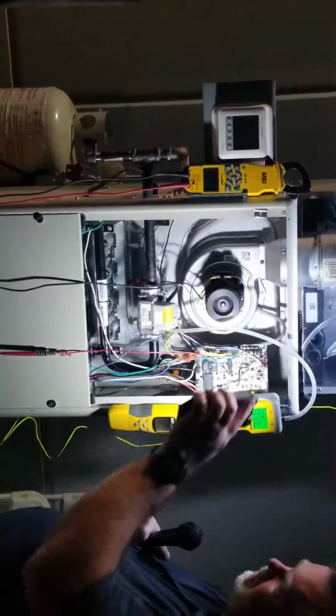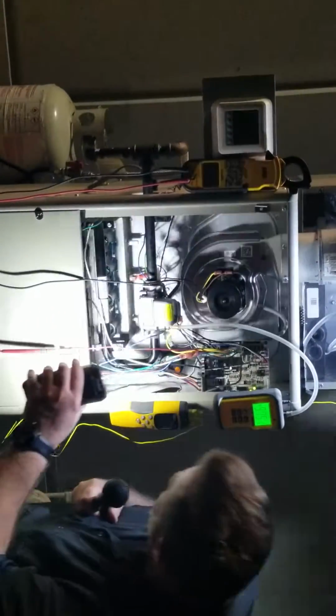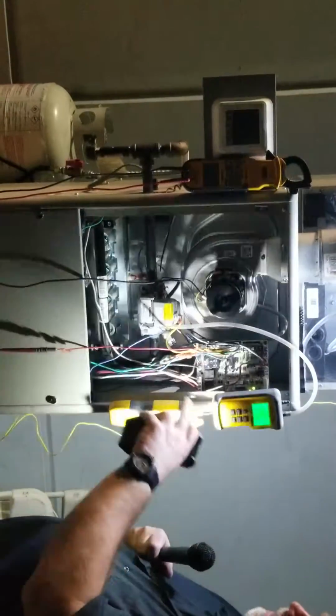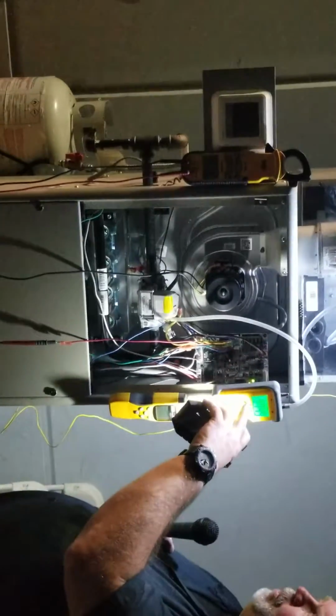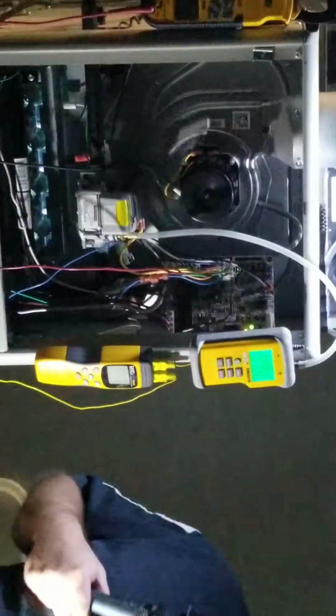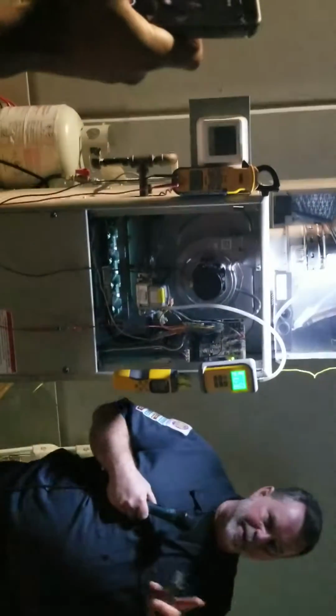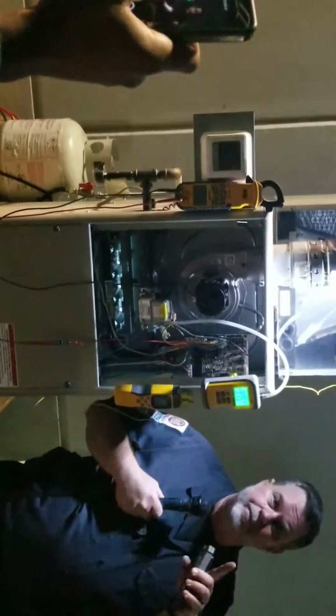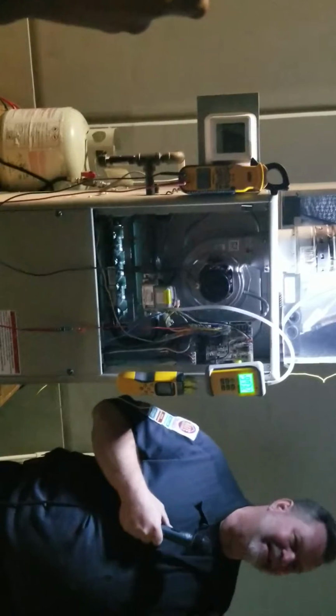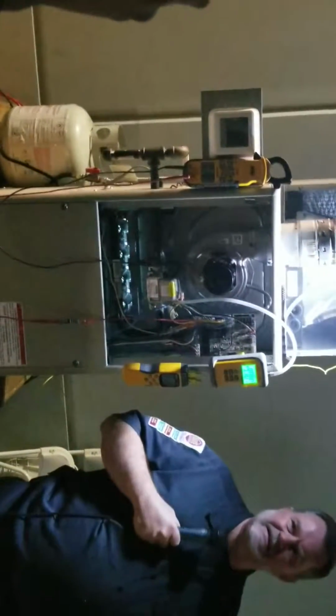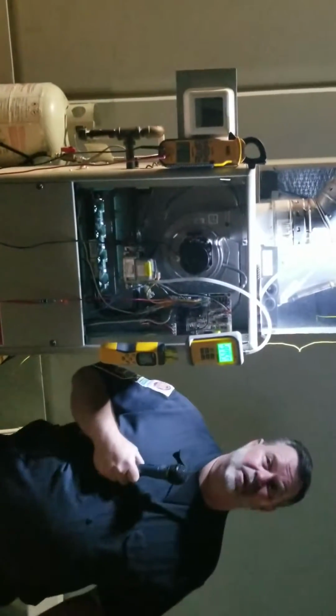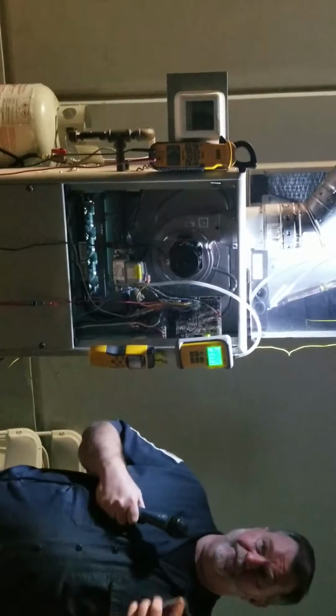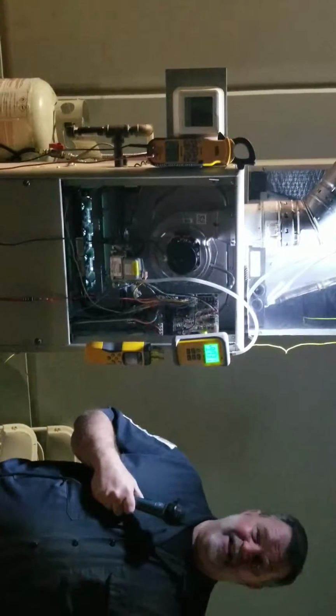After it's lit, notice that I've got my manifold pressure at 9.75. This is propane. This is not natural gas. I converted this to propane, actually JC did. The outlet pressure, instead of 3.5 for natural gas, on propane is supposed to be between 9 and 11. Does that make sense? Why is that? Because it's a different fuel. It's a different oxygen and fuel mixture. It's just not the same.